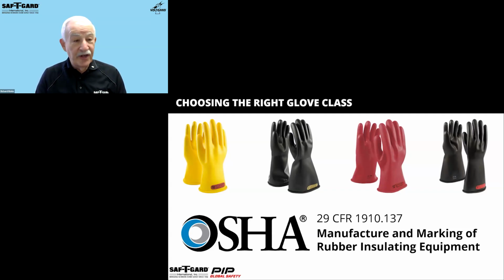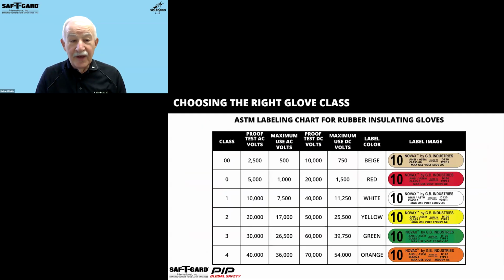Each specified hazard assessment will help in determining which class of rubber insulating gloves is appropriate for the application. So take a look at this. Look at a very common glove. Let's look at the class 0 glove. Those gloves are tested at 5,000 volts AC, but the maximum use voltage is 1,000 volts AC. That's a heck of a margin of safety. The same for if it's a DC test, and we'll talk about DC in a few minutes. Those gloves get a test at 20,000 volts DC with a maximum use voltage of 1,500 volts DC.